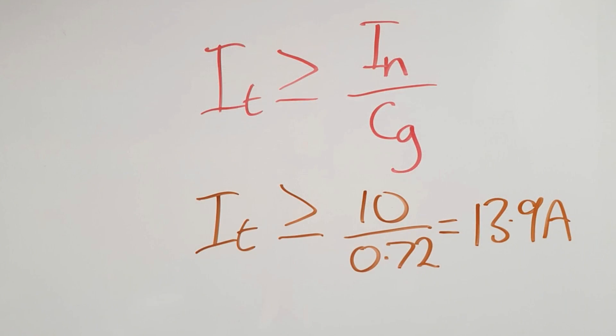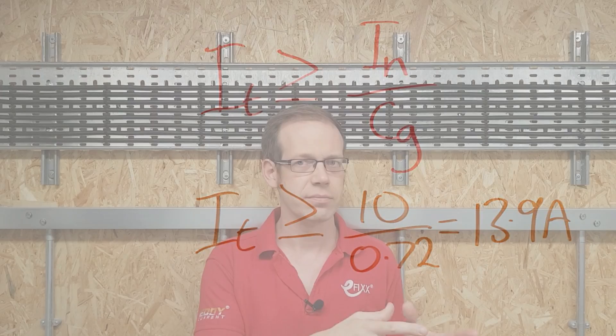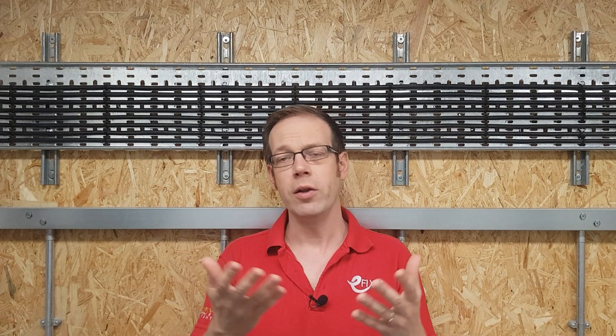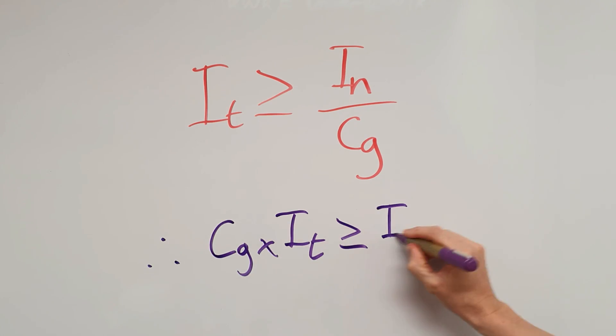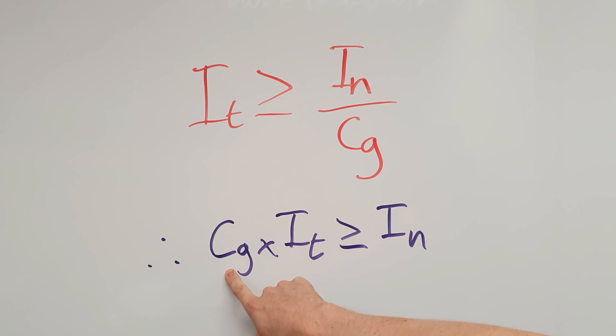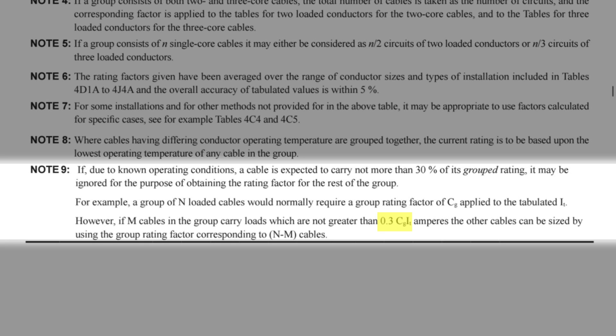So let's try and unravel that. The note is telling us that the grouping factor needs to be applied to the tabulated current carrying capacity of the cable, but earlier we applied the grouping factor to the nominal rating of the protective device — so what's going on? Well, looking back to our formula, if we transpose it we'll find that the current carrying capacity multiplied by our grouping factor must be greater than the nominal rating of the protective device. So if the grouping factor times the tabulated current carrying capacity times 0.3 is higher than the current expected to flow, then you don't need to count that cable in your grouping calculation.